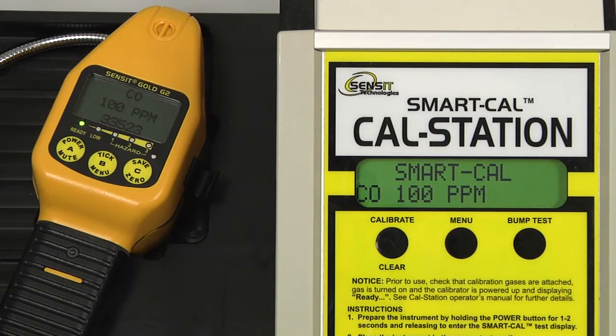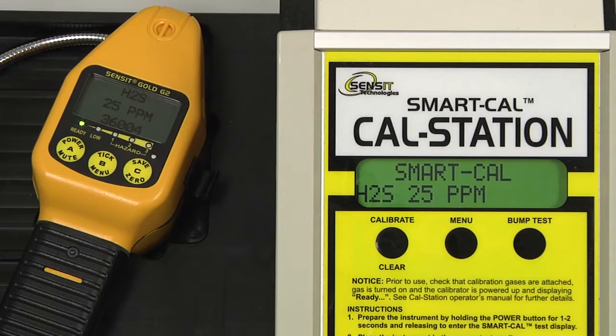100 parts per million CO is now being calibrated. Followed by 25 parts per million H2S. Followed by 100% by volume methane. And finally a brief O2 test, since this instrument is equipped with an O2 sensor.